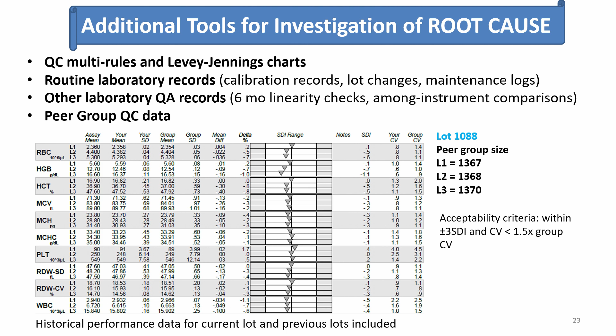So if we have a QC failure on one instrument and see that the 2 other instruments' QC is about to fail, we probably have a problem common to all those instruments, like the reagents. Another really useful tool is the peer group QC programs. Of course, Bio-Rad has one. This one happens to be Sysmex. This is where the lab will submit its QC data in real time, and you get a real-time comparison to your peer group on your particular reagent lot. So this can be very useful for troubleshooting.